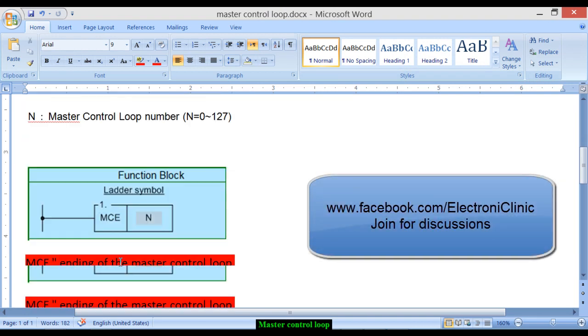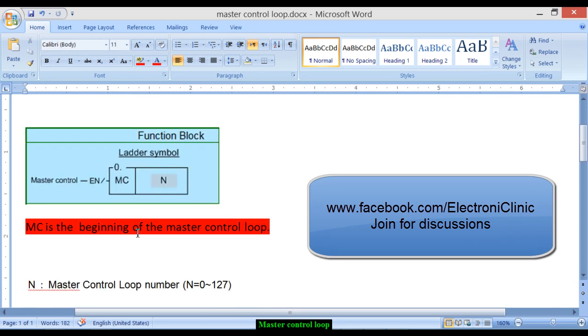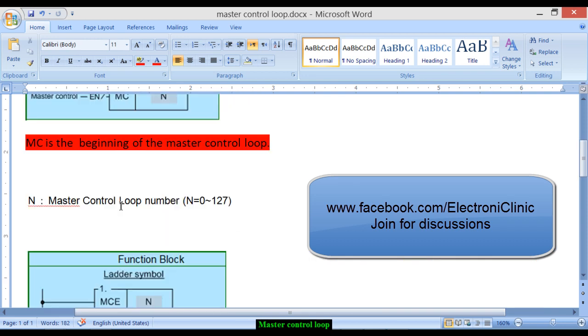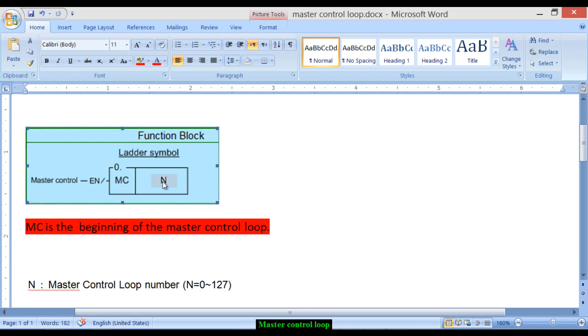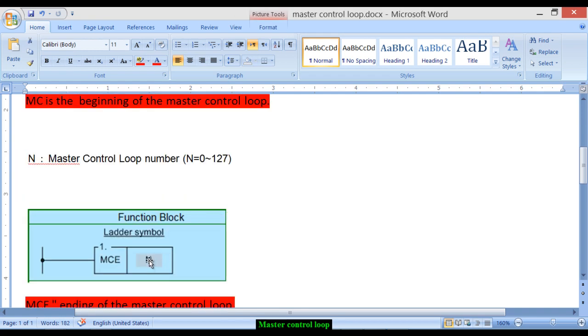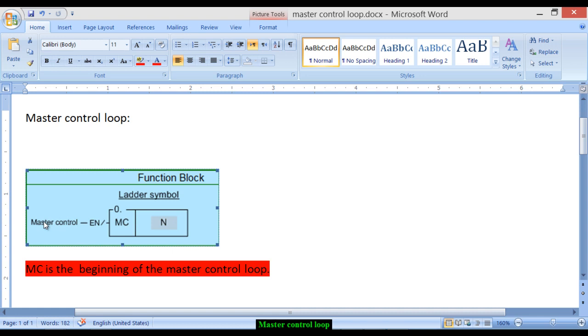Every MC has a corresponding MCE, which is the ending of the master control loop. The MC and MCE are always used in pairs and must have the same number. For example, if you use number 2 for MC, the same number 2 must be used for the corresponding MCE.